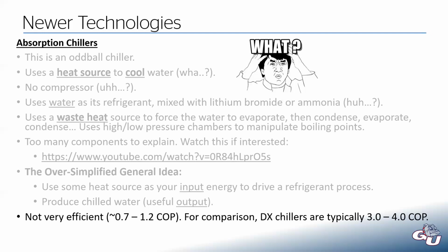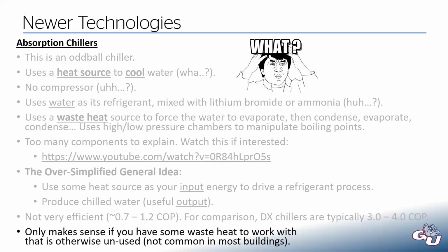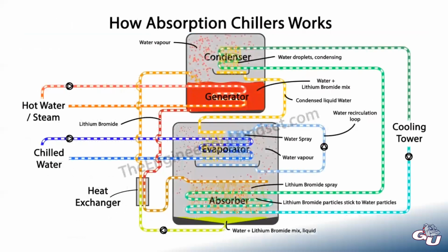So why would you ever use an absorption chiller as opposed to a standard DX chiller? Well, this makes sense if you have some waste heat to work with that's otherwise unused. Let's say you have some hot water that results from some process in your factory. Whatever process you have produces this hot water, and you just dump it outside because you have no other use for it. Well, in that case, you're dumping a lot of energy outside because this water is really warm, so why not instead send it to an absorption chiller, assuming you need chilled water at your building as well. So this is all the parts and pieces of an absorption chiller. There's a lot going on here.